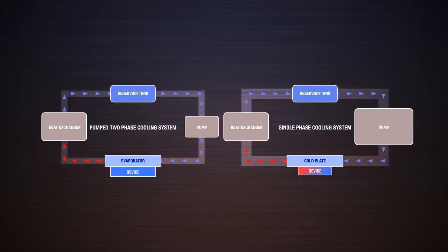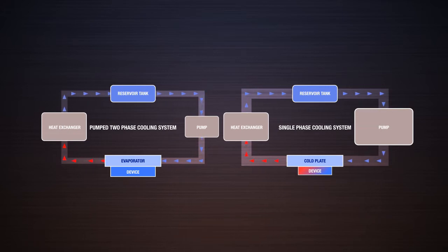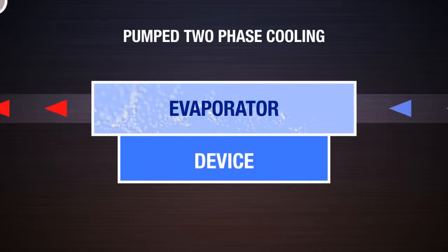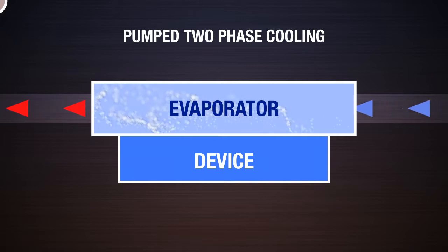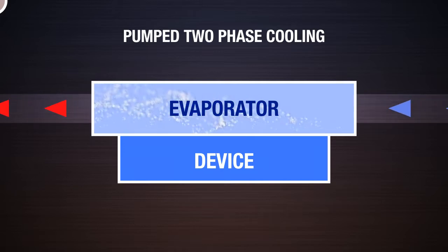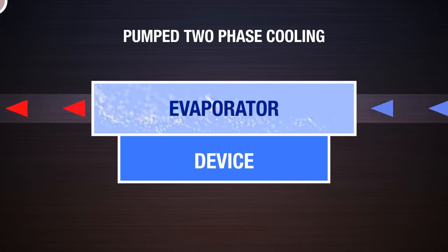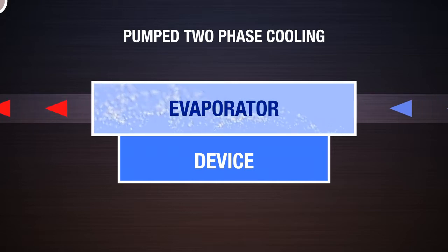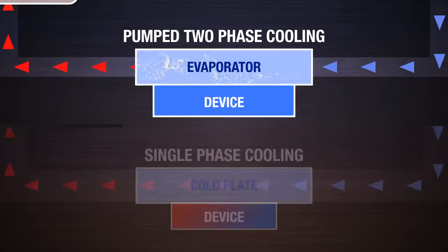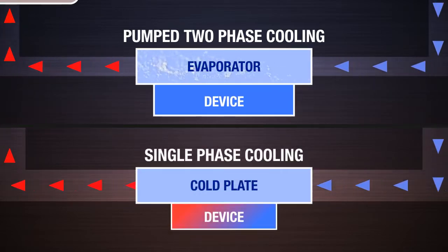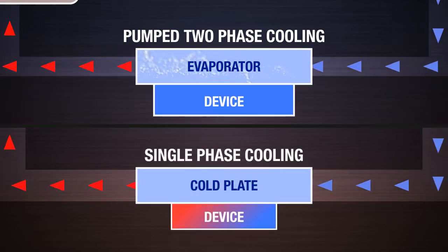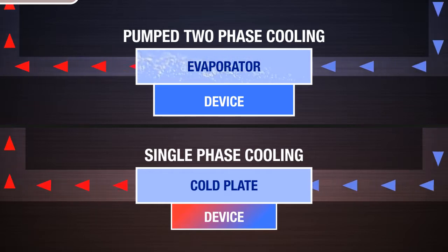Pumped two-phase or evaporative cooling systems use the same basic system-level components as the pumped single-phase system. However, pumped two-phase systems typically use refrigerants as the working fluid. Through refrigerant selection and appropriate controls, the refrigerant is designed to boil as it acquires heat from the hot surface of the device. More heat can be removed through the boiling process, otherwise known as latent heat, than through sensible heat with single-phase cooling.